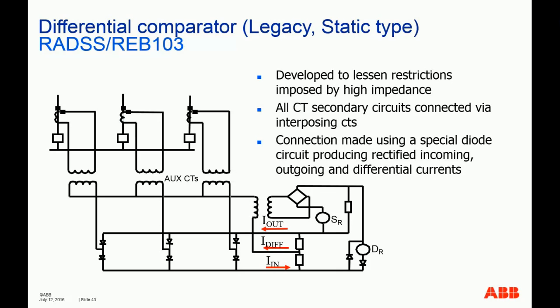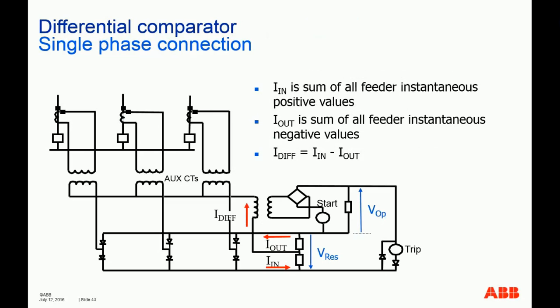Okay, so basically, imagine if you have an external fault and all the current is going in the same direction, but for one CT, all the current is taking the exit off. So that current will be the out, and the other one will be the in. Okay, and the differential obviously is the in minus out. Okay, it's a vectorial sum of the two. I'm not going to touch too much on this.